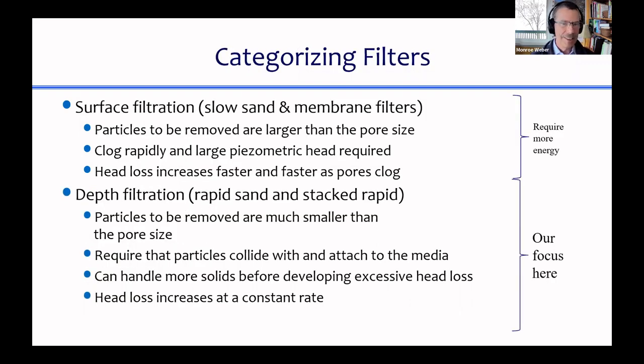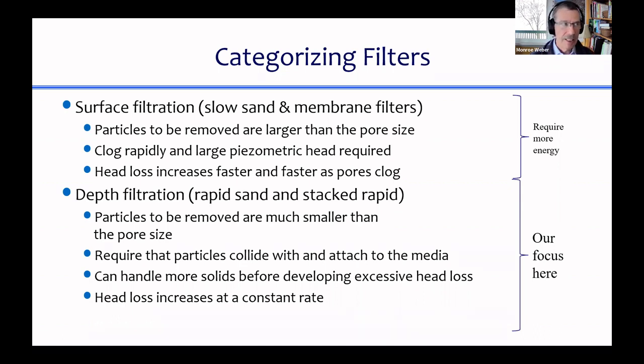Most municipal water treatment plants in the United States use rapid sand filters. They are depth filters. There are also many plants beginning to use membrane filters — a transition that's been happening for the last few decades. Membrane filters have pores in a plastic membrane, and the pores are so tiny that they can capture all the particles you would want to remove from the water. The pores are smaller than bacteria, so they will absolutely capture those bacteria.